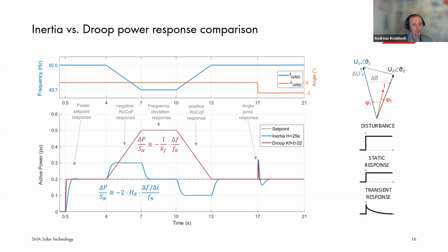In that case, it is possible with our controls to combine both responses so that they act simultaneously. And for power grid stabilization, of course, you need both of them. But the advantage of our control mechanism is that we are capable of separately distinguishing between these two and adjusting them independently, which might be very effective in the provision of grid forming services of different types to the power system.